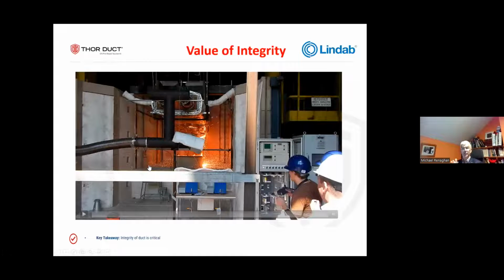Okay, integrity. Let's deal with integrity. So we have a fire. The fire's raging. We're exhausting the smoke from the scene of the fire. It's passing through the duct. That can be quite hot. That can go up to 800, 900, 1,000 degrees. What does that do to the metal? Well, with all solids, it effectively moves them to gas, or along that chart. And so we need to protect all around us from that heat overload. So we just wrap the duct with an insulation, except the performance of the insulation is directly related to the performance of the duct because it's connected to it. So if that duct moves, suddenly you've got a problem. So I just want to show you a very quick example of a problem duct in a fire.